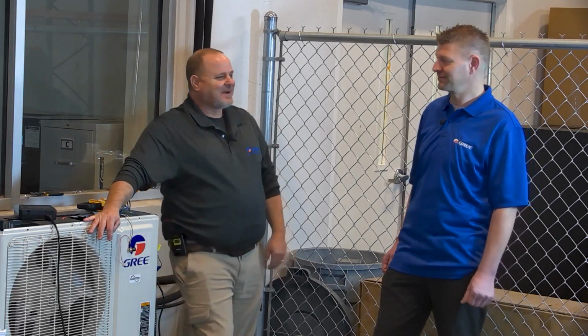But the discharge temperature couldn't have been out of line because it was at 50K. Right. Because it was looking for it to increase and it didn't increase. There you go. You can't lie to this machine. It's going, wait a minute. No. With the way the compressor speed is, with all the stuff this thing is doing, that discharge temperature ain't moving. There's something wrong here. So you can't cheat it.